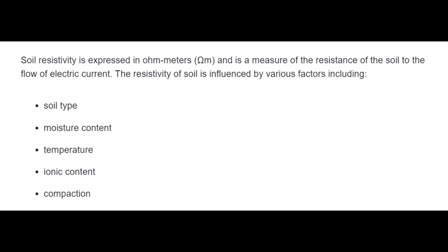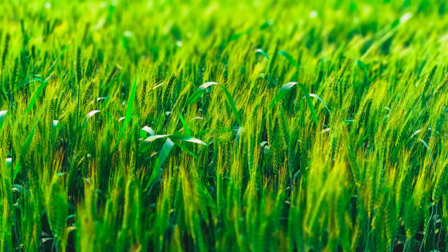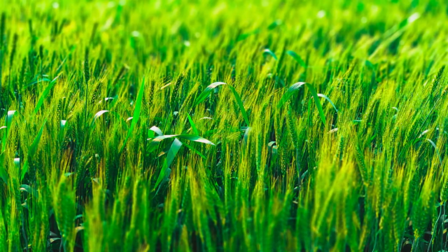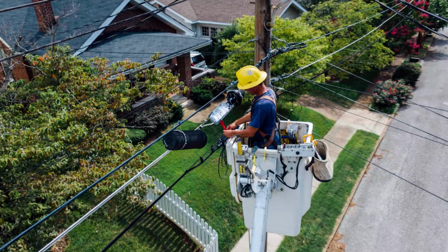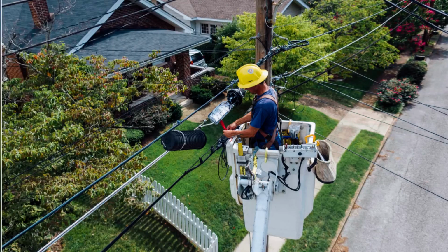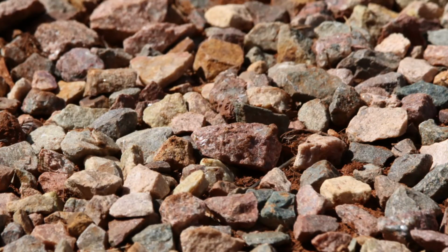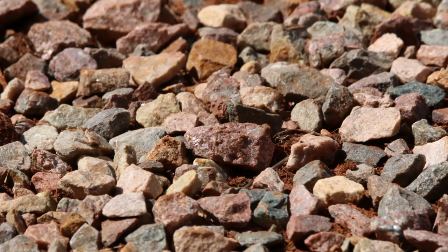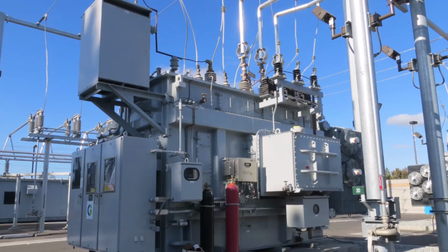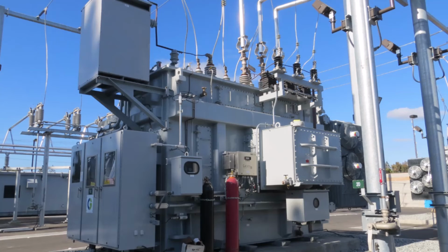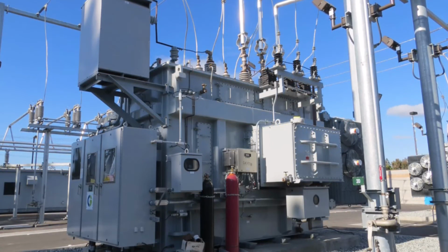and compaction. A lower soil resistivity means that the soil is more conductive and is better able to conduct electrical current. This is desirable in grounding systems where a low resistivity is required to ensure that electrical charges are safely dissipated into the earth. Conversely, a higher soil resistivity means that the soil is less conductive and is less effective at conducting electrical charges. This is not desirable in grounding systems as it can result in higher resistance, leading to increased risk of electrical shock and other safety hazards.